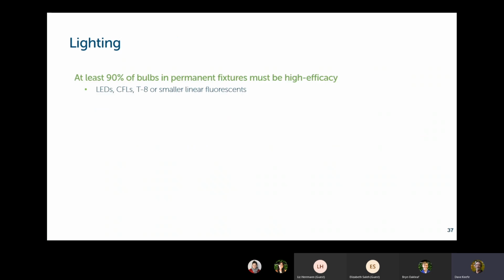At least 90% of the bulbs in the building need to be high efficacy. That means, in a practical sense, something better than an incandescent. So CFLs still meet that requirement, and the modern smaller diameter linear fluorescents also meet it. The old style larger fluorescent tubes that were 1.5 inches in diameter, the T12s, do not meet this requirement, but the smaller T8s and T5s do.